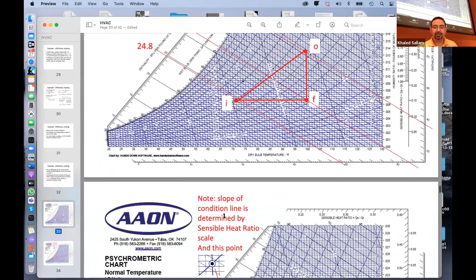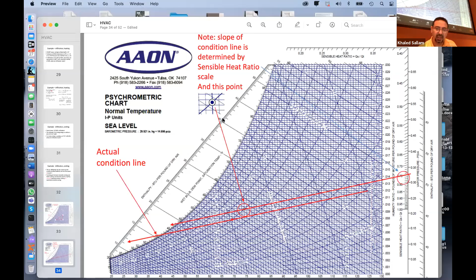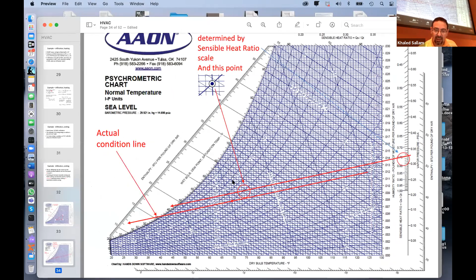So that's where this chart comes in. Those scales, some of them come with protractors, some just come with this, you know, the way to read that scale. We talked about this last time, so let's stress this again. This is QS over Q total, Q sensible over Q total. So if you are standing here at that point and you put a line like this and it goes to 0.75, that means your sensible load is 75% of the total.